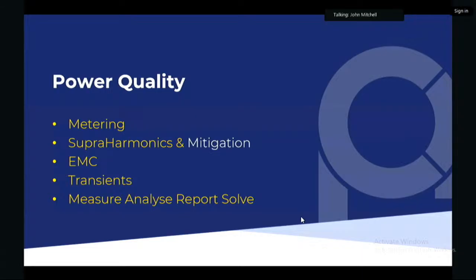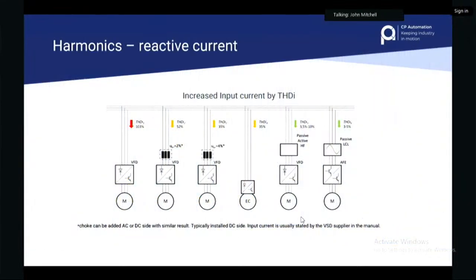So now we get on to mitigation. And forgive me, this is a lot of information really quickly, and I'm not there, so I'm conscious that some of this might be new, and for some of you it isn't, so forgive me. This is just explaining the different drive technologies. So you have variable speed drives with chokes. You can have EC fans for data centers and chillers. And then you've got variable speed drives with a passive filter or an active front-end drive with also a passive filter, an LCL filter. And these are the different technologies that would give you a different THDI, which is the current distortion going into the transformer.